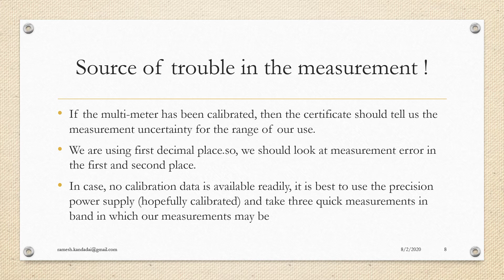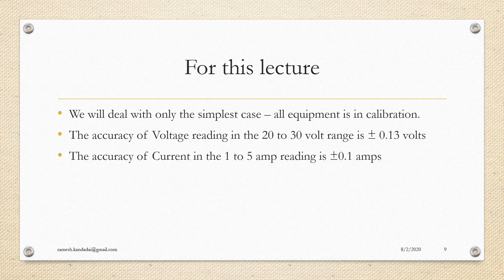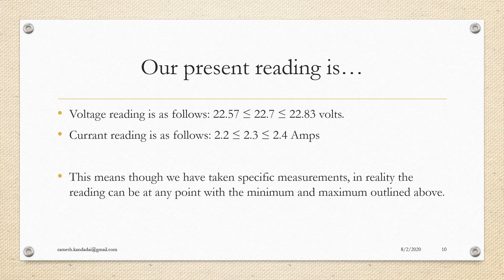We have now verified the calibration certificate on the multimeter, and we have found that the accuracy of the voltage reading in the 20 to 30 volt range is plus or minus 0.13 volts. Similarly, the accuracy of the current in the 1 to 5 amp range is plus or minus 0.1 amps. So what this says to us is the voltage reading that we have taken as 22.7 volts could be anywhere from 22.57 to 22.83. The current reading, which you have noted down as 2.3, can be anything from 2.2 to 2.4. Any point on that range of 0.26 volts in the voltage and 0.2 amps in the current is equally valid as any other point.